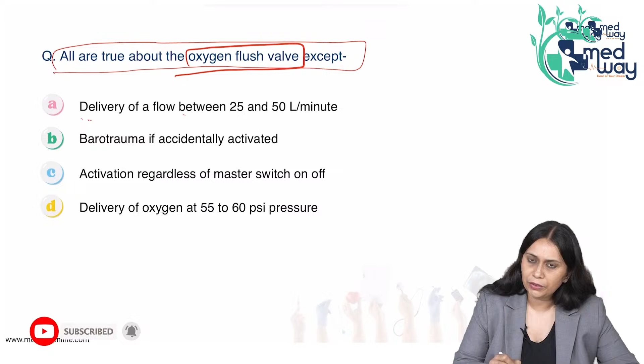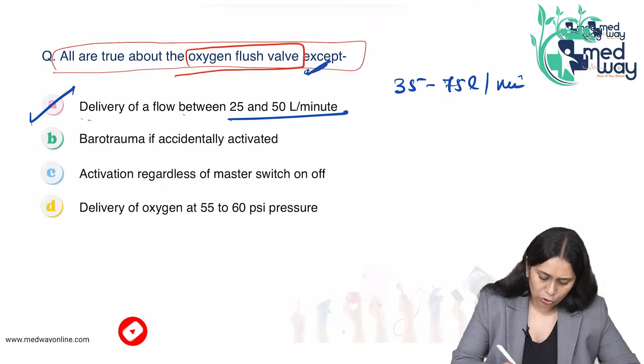Delivery, all true about it except delivery of flow between 25 to 50 liters. What I just now said, between 35 to 75 liter per minute. So, this is incorrect. So, this is not true. So, this would be the answer. Barotrauma, if accidentally activated, our lung can tolerate 10 to 12 psi. Here it is giving pressure at 45 psi. So, there is a risk of barotrauma.